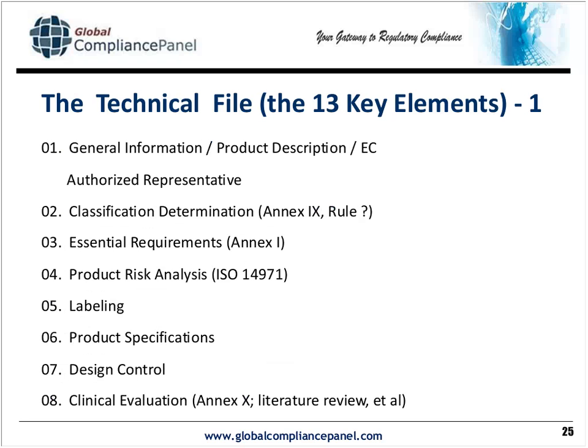The technical file, I list 13 elements. That may vary depending on your notified body, but basically you have a description of your product, a determination of its classification based on Annex 9 and whatever rule applies, and then that you've met the essential requirements. I usually use a matrix to cover all of them and NA those that are not appropriate, and that's Annex 1 of your Medical Device Directive. A product risk analysis, and that's ISO 14971.